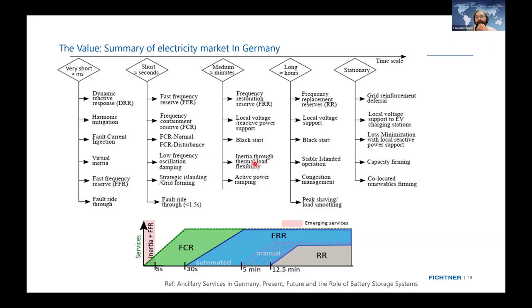And what else? In stationary applications, we have grid reinforcement, and local voltage support to EV charging stations, which is my PhD work, and local loss minimization with local reactive power support, such as my inverter being used as a 100% reactive power source, with power factor from 0.9 to unity. I can go positive, I can go negative, so I can provide reactive power support.